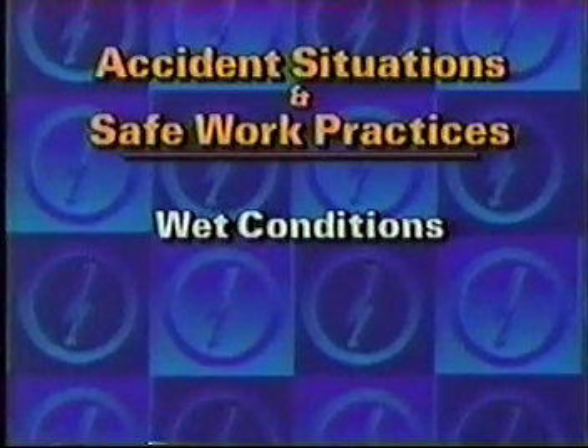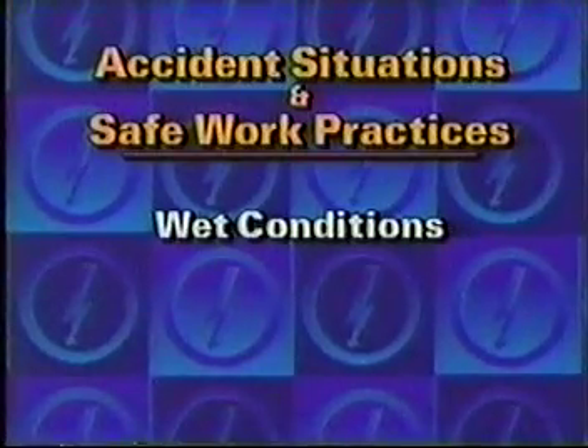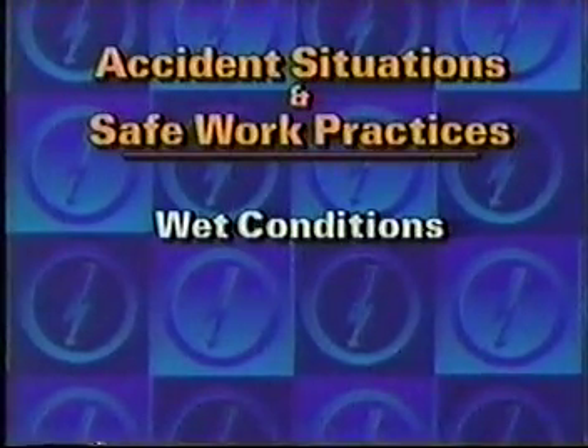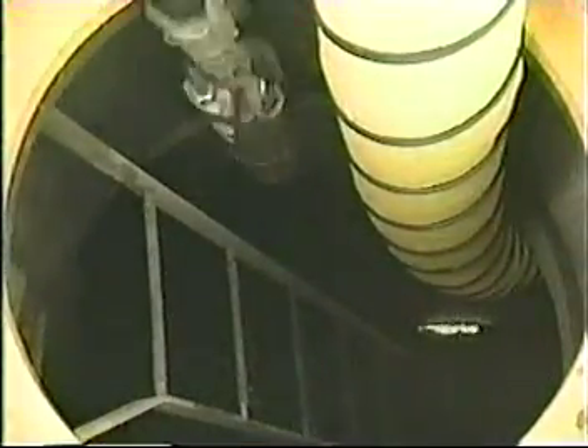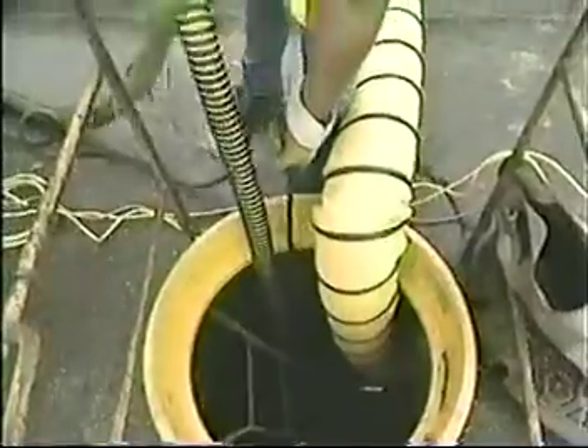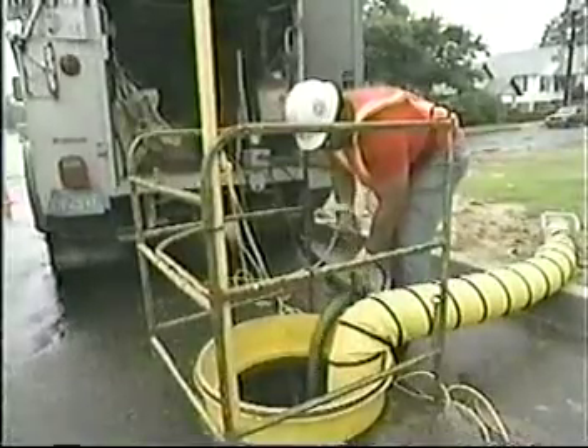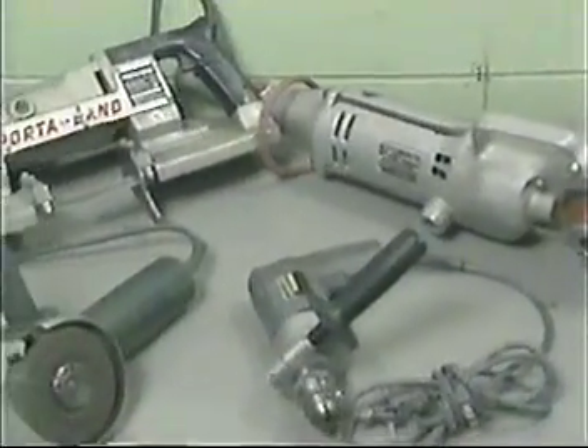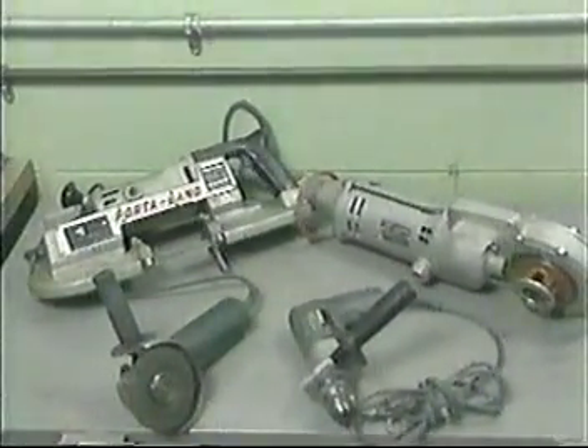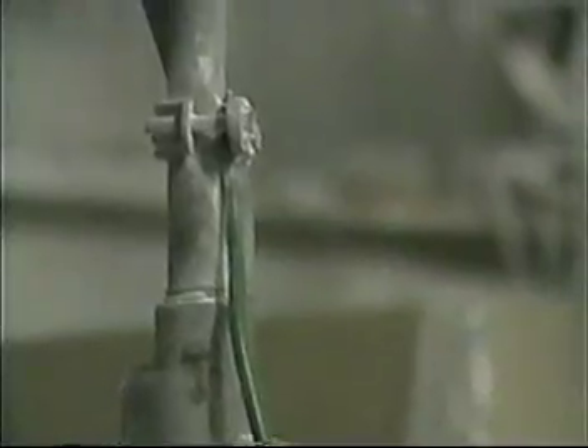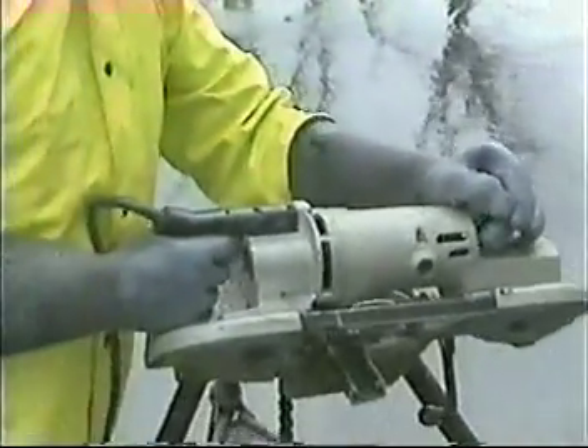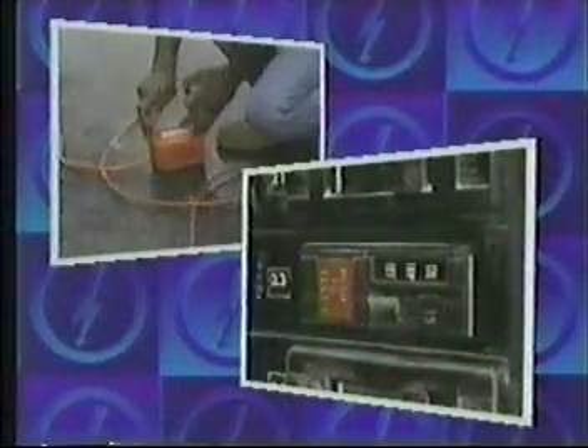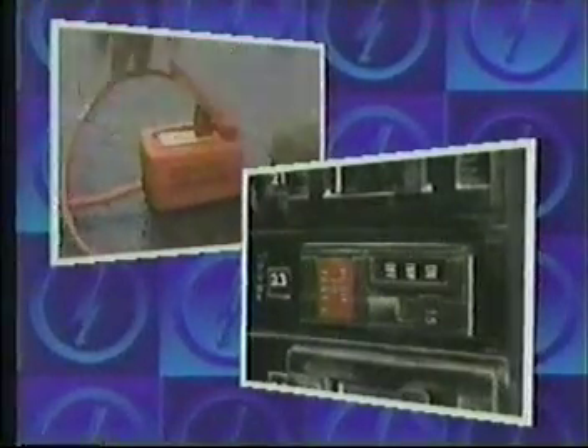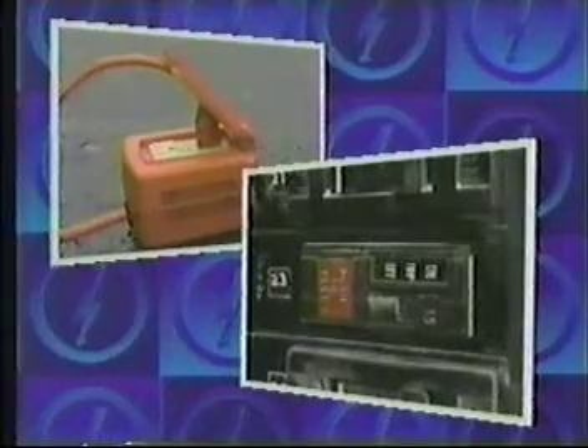The next category of accident situations we'll consider are those involving working in wet or even damp conditions without the proper equipment. Water and many other liquids are conductors, so extra precautions must be taken when electrical equipment is used in a wet environment. First, use only equipment that is specifically designed and rated for use near water or other conductive liquids. Be particularly careful to follow all recommended grounding and bonding procedures. Wear tested and inspected insulating gloves and boots rated to provide adequate protection. Whenever possible, connect your equipment to a ground fault interrupter. As we've already seen, this extremely sensitive device provides some degree of protection.